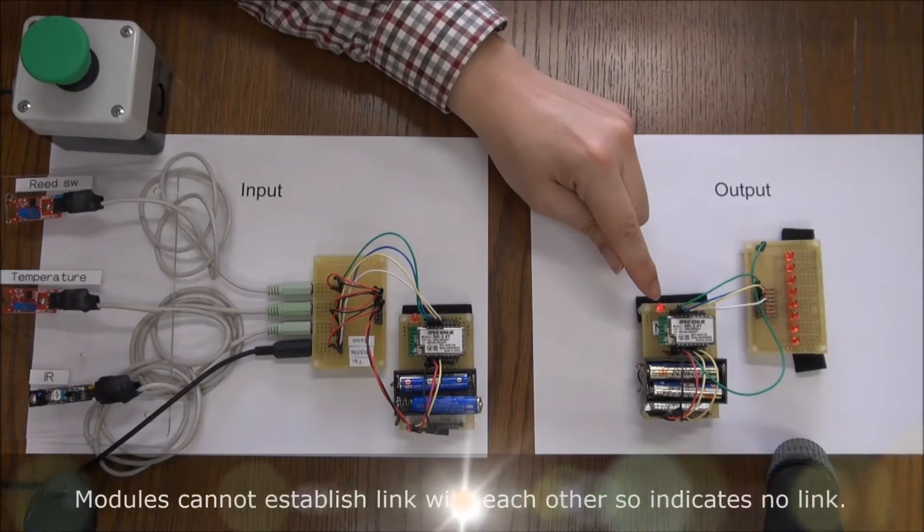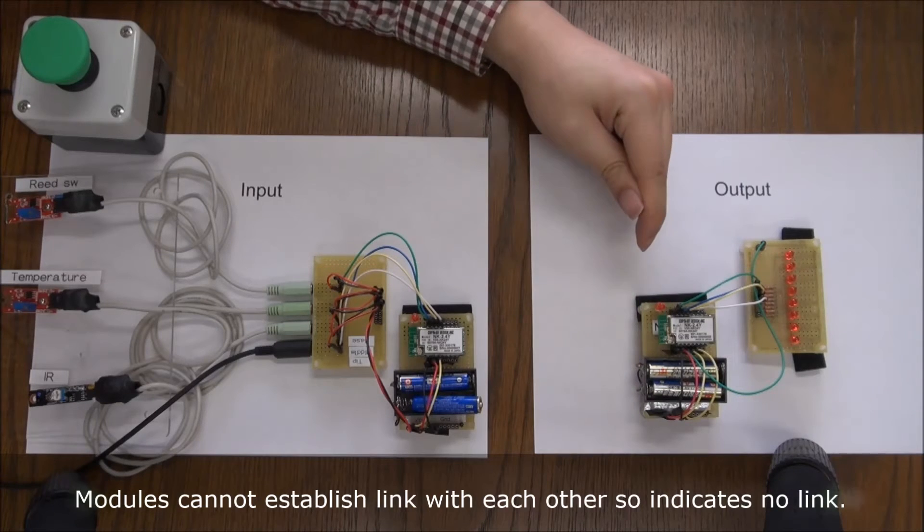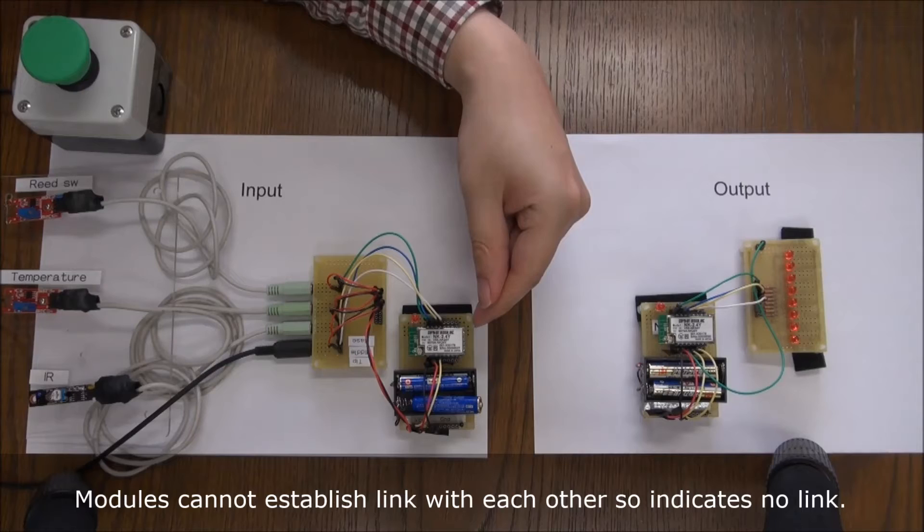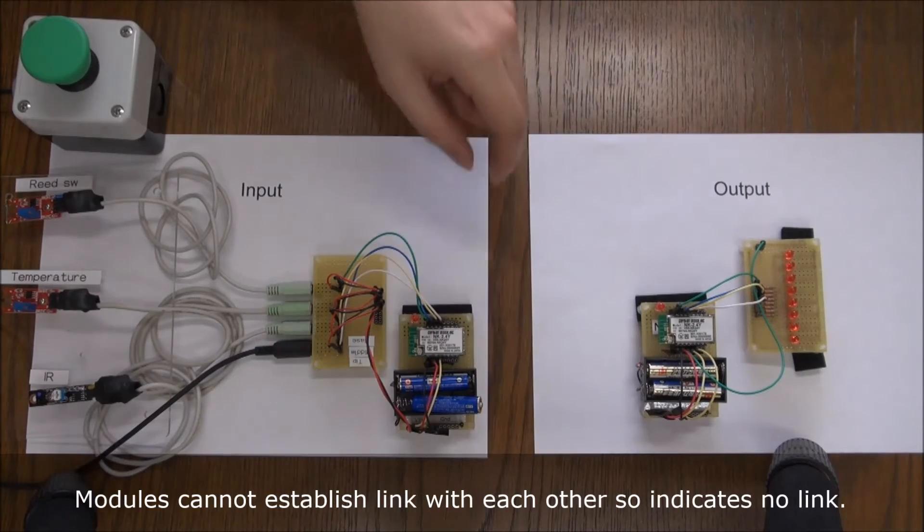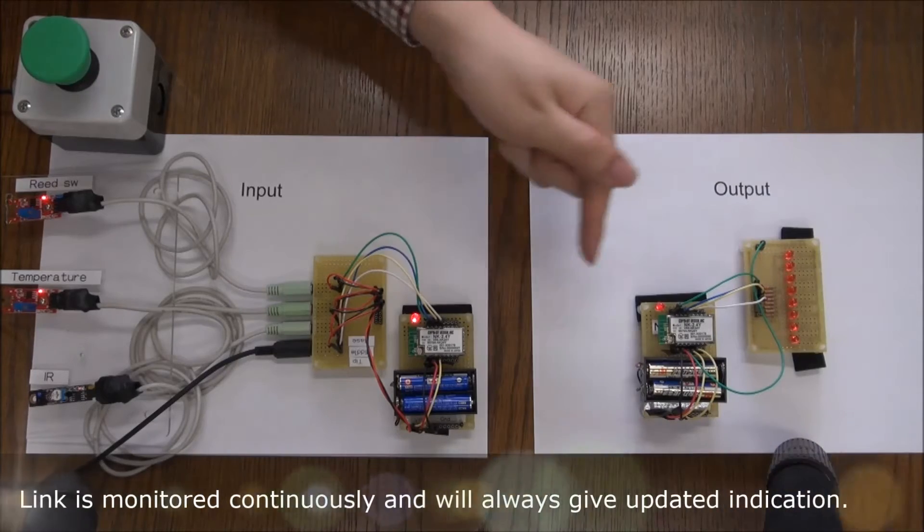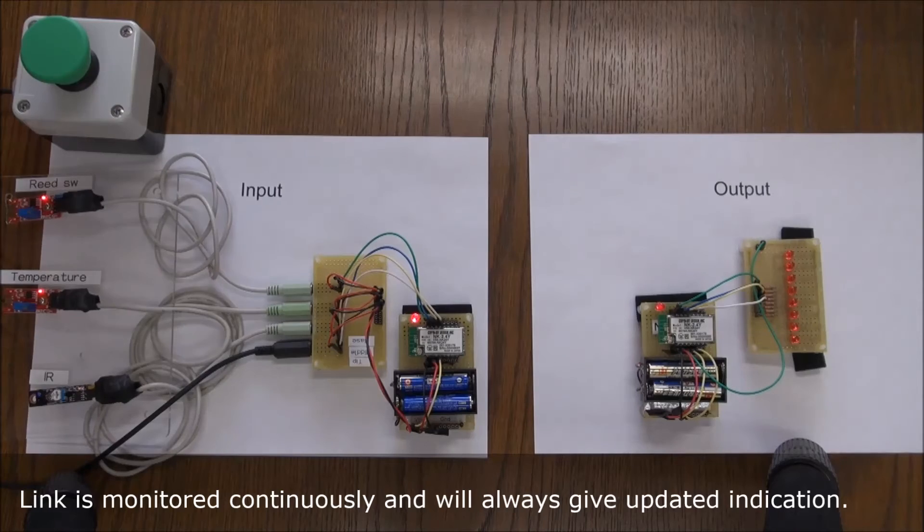We can see a flashing LED means the link has been broken, and this module can no longer see the link to this one. Now, if I put the battery back in, you can see the LEDs come back on steady, which means the link has now been established.